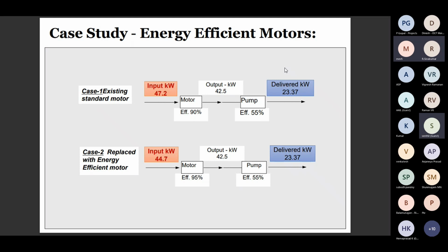One case study: the existing motor can be replaced with an energy efficient motor. This is a pump application, and the delivered output is the same here. In both cases the delivered output is 23.37 kilowatt. The existing motor consumes 47.2 kilowatt because the motor efficiency is 90%, so the 47.2 kilowatt input is converted to 42.5 output. The pump efficiency is the same 55%, so the pump output is 23.37 kilowatt. Whereas the energy efficient motor takes only 44.7 kilowatt. The motor efficiency is higher, so for the same 42.5 output the input power is less, with the same delivered output.